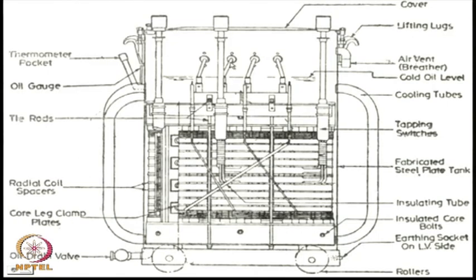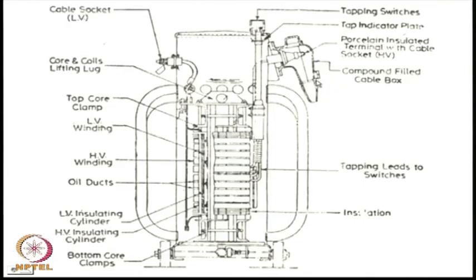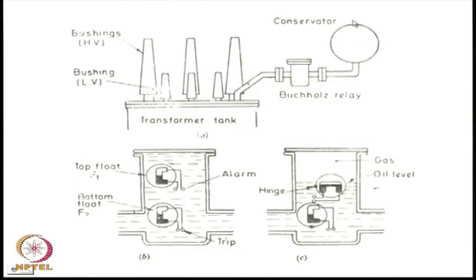The second view is the front view. This mostly shows the other auxiliary connections, for example, the cover, the lift lug, and there is an air vent or breather. Note that there is a conservator on the top of the tank. Normally, the tank will be completely filled with transformer oil. In fact, the transformer oil will also fill the Buchholz relay, and will possibly end somewhere here.